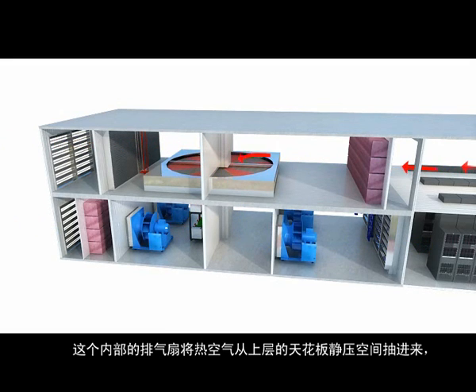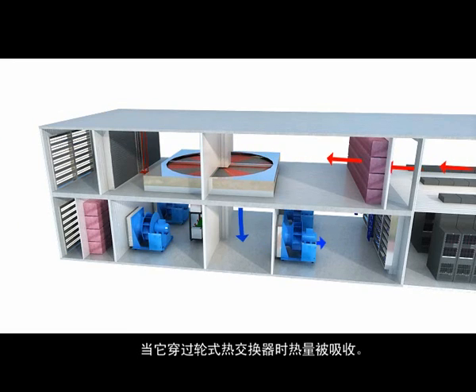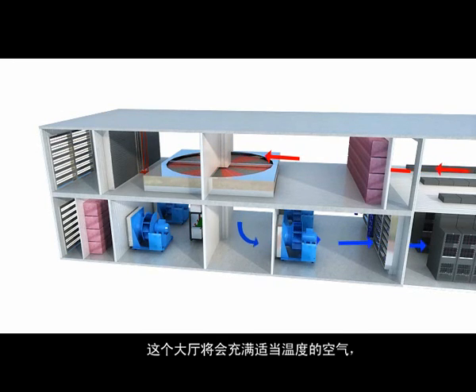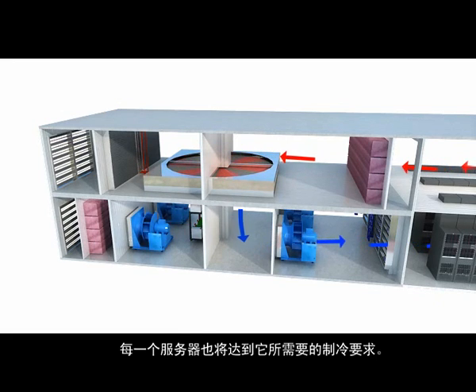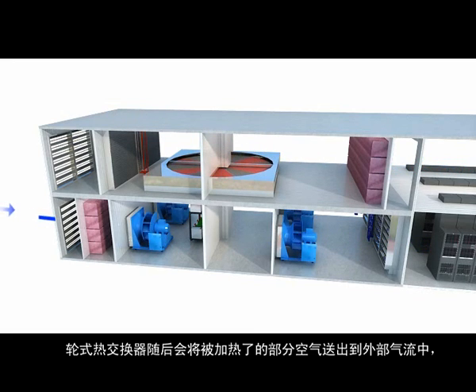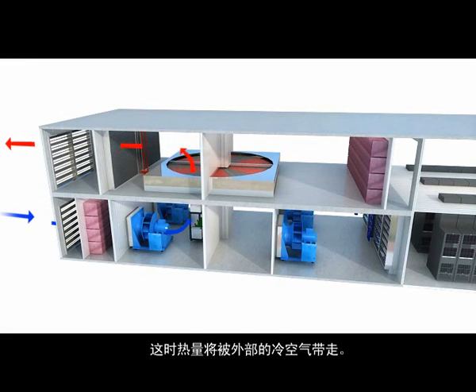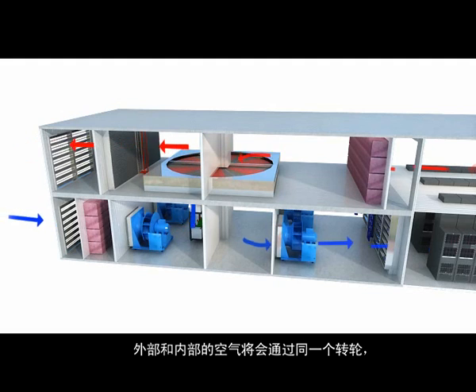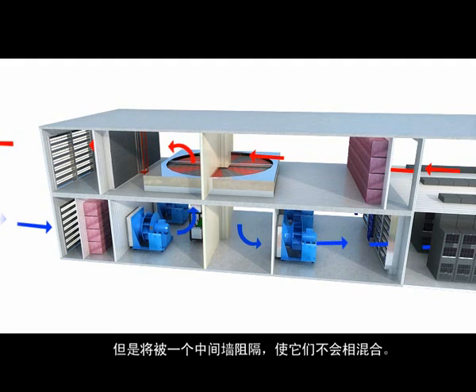The inside air fans pull heated air from the ceiling plenum and move it through the heat transfer wheel, where the heat is absorbed. The cooled air is then delivered gently back into the data hall. The data hall is simply filled with air at the correct temperature for each server to draw on as required to meet its own cooling needs. The wheel then rotates the heated section into the outside airstream, where the heat is removed by cool air from the exterior. The outside air and inside air pass through the same wheel, but remain isolated by a center wall to keep them from mixing.